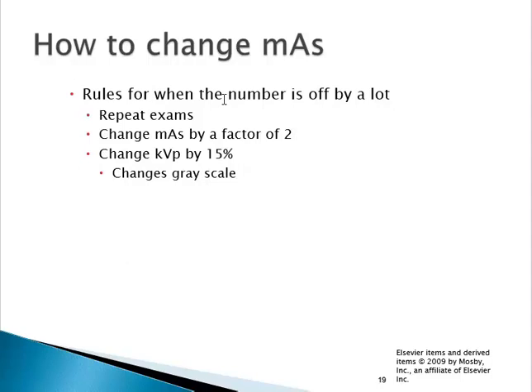If you need to change by a lot — for example, double your exposure — you go up by a factor of 2 in mAs or 15% in kVp. That factor of 2 is a 100% change. Or if you overexposed and need to repeat, cut back by at least a factor of 2, or reduce KVP by about 15%. The problem with changing KVP is it might affect the grayscale — it might affect your contrast.